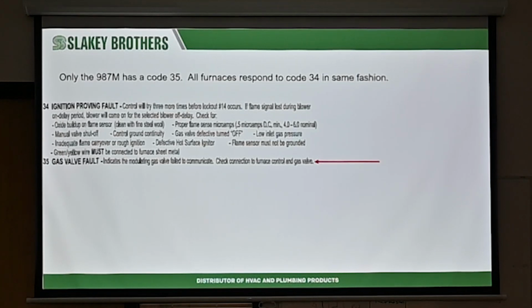Usually on startup, everything is fine. The most common thing on startup for you guys that I see, people overlooked it, didn't pay attention, is that yellow and black tubing. The black is for your pressure switch. Yellow attaches onto your P-trap, and it's just an extra vent. It's just venting some of the pressure a little bit out of the drainage overall. Okay? I had one guy that swapped these by accident. So his pressure switch would never close because it was never hooked up to the collector box. It was hooked up to the condensate drain instead. Once he sent me a picture and he flopped it over, it was a miracle. It started working just fine. But for install, that's a very common thing.